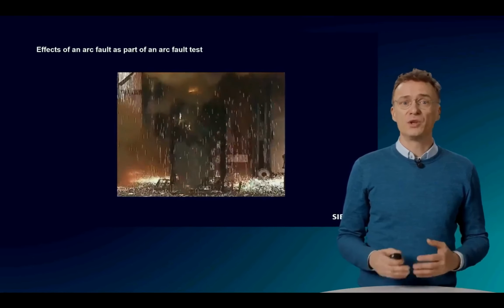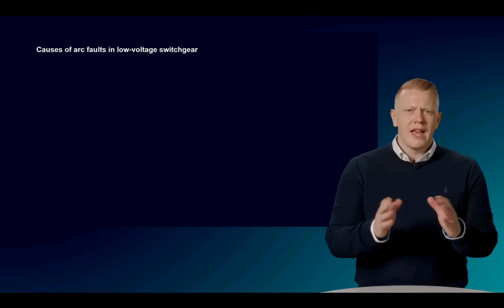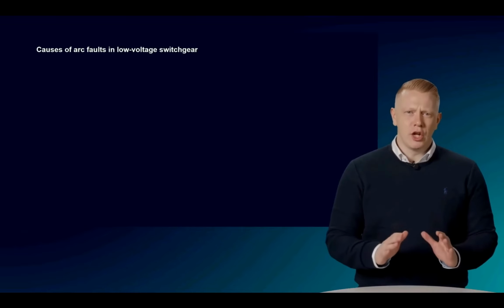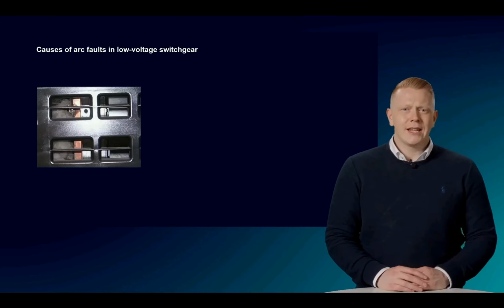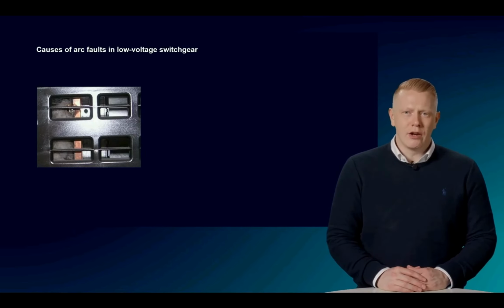In this short video, you can clearly see the destruction that comes from such an event. That's very impressive. It is also important to know how such incidents can occur. First of all, arc faults are very rare. They represent an absolutely exceptional situation. In practice, however, we see a wide range of possibilities as the cause of arc faults. On the one hand, these can be, for example, external circumstances such as pollution, which means that the insulation properties in the switchboard are no longer guaranteed. This can be, for example, also by animals that can enter the system and cause a short circuit.